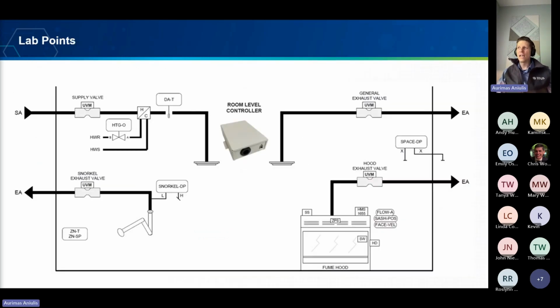This is a typical lab scenario that you would see. You have your supply valve, your general exhaust valve, your fume hood exhaust, your fume hood, and a snorkel. From this point on, most applications are just a quantity increase of said items. You might have multiple supplies, multiple general exhausts, and multiple fume hoods. It's not unusual for university teaching labs to have 10 or more fume hoods, which will require multiple supplies and sometimes even multiple general exhausts. Some industrial laboratories have hundreds of snorkels in different bays, and that in itself is an interesting application to be talked about.